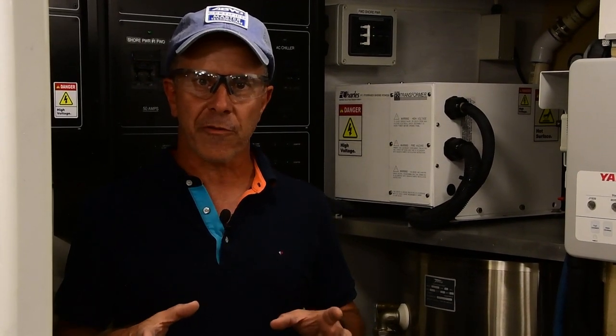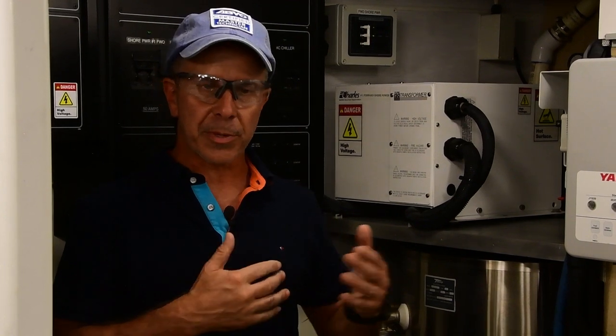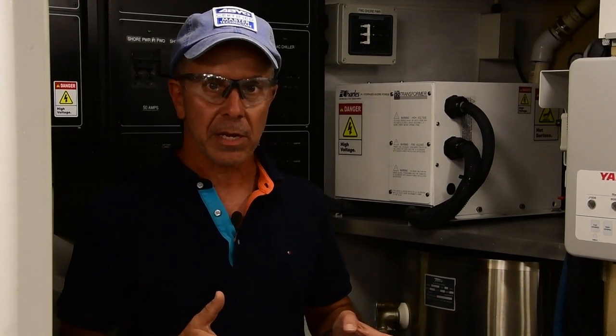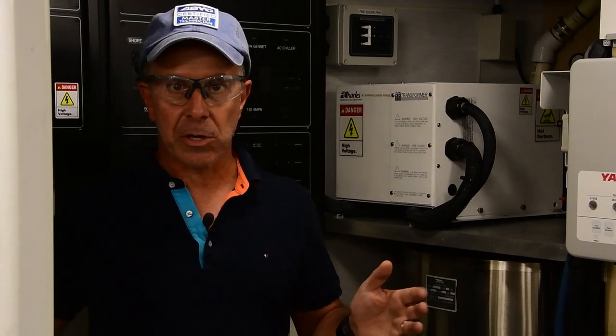Another potential benefit of a shore power transformer is its optional ability to boost low voltage. Why would that be important? Well, traditionally, if your vessel is wired for what we call split phase, otherwise known as 120 volt, 240 volt, if it's wired for that type of voltage, it's possible to plug into a dock that is providing, instead of 240, 208. It's fairly common in North America to encounter this. So that means that the equipment on the boat that's designed to run at 240 volts would instead run at 208, sometimes less because of voltage drop.